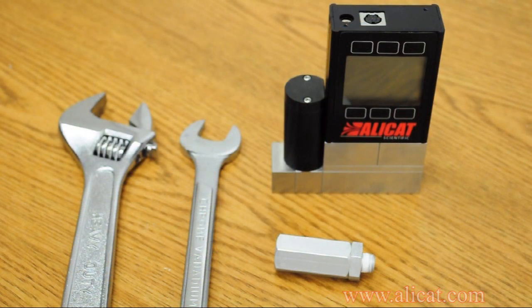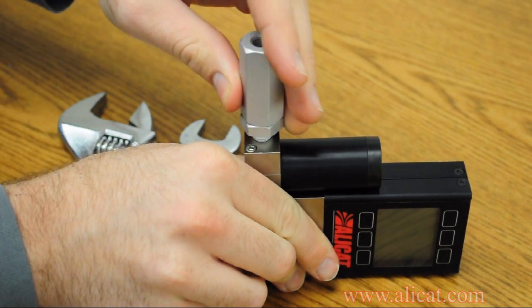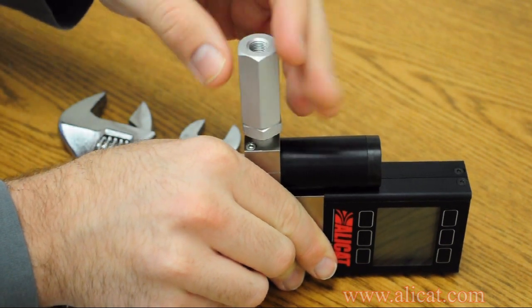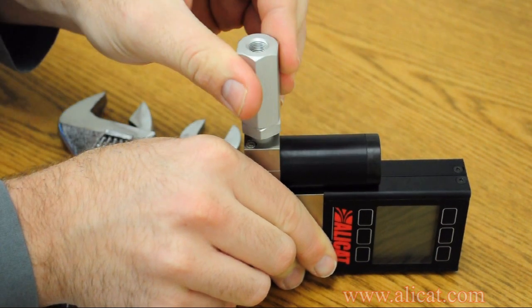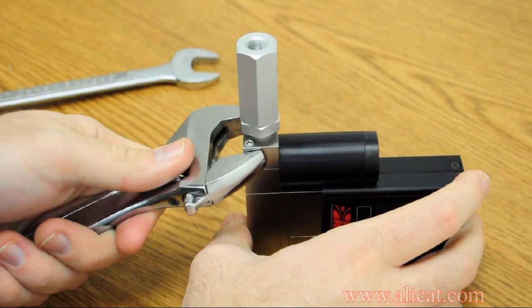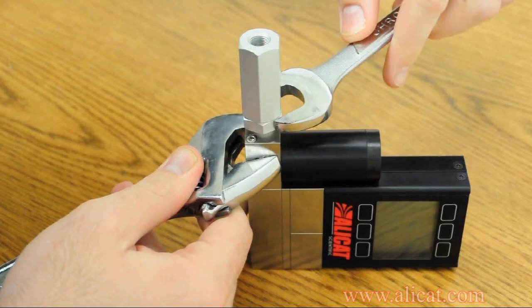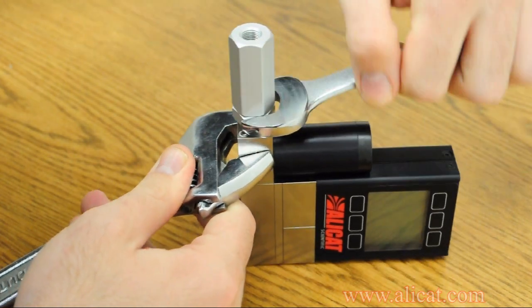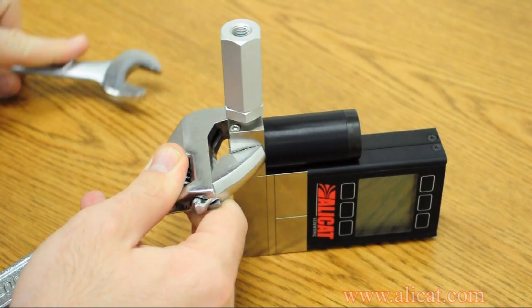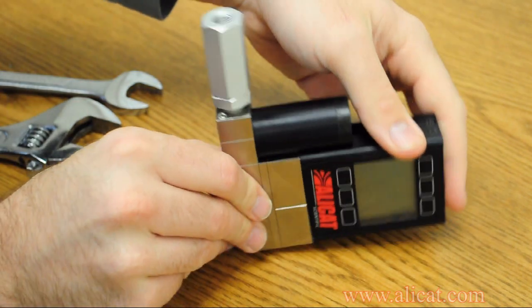When installing a factory-supplied inline filter, follow the general procedure for Teflon tape application. Then, screw the filter clockwise into the inlet of your instrument. Tighten the filter using two wrenches, one to hold the inlet port block and the other to rotate the filter until tight. Do not use the black valve assembly as leverage when tightening. Take care not to over-tighten this filter or any fittings used on your Alicat product.